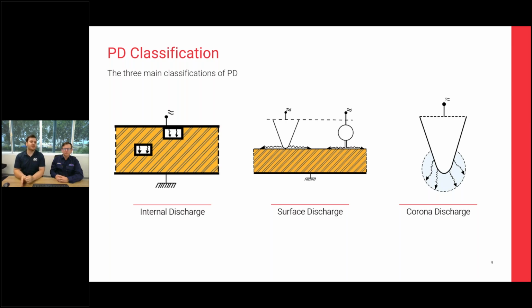The reason this becomes so prevalent is that you also have to consider what failure modes we are looking for within the terminations. One of the things we discussed at length is that the types of test methods we use have to follow the types of failure modes we're looking for. Traditionally, internal type discharges are found using the TEV method, the transient earth voltage method. Surface discharge and corona are primarily found using ultrasonic testing. But when we discussed the types of failures we're trying to look for and prevent, it's going to be primarily those internal type discharges. It's going to be problems going on within the oil or within sealed insulation that we cannot easily ultrasonically test.